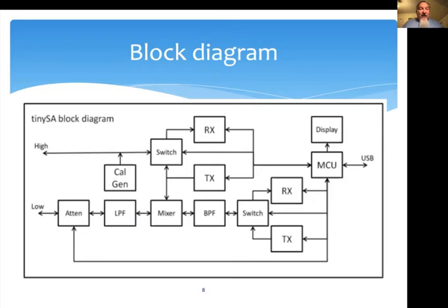So there is this attenuator as a first stage. Also, as I'll mention later on, the attenuation is quite important to condition the input signal into a range which reduces, as far as possible, the presence of artifacts and spurs. It then goes into a low pass filter according to the frequency range or the measurements that you're doing. And the purpose of the low pass filter is mainly to cut out any noise at higher frequencies that you're not interested in. So it's kind of a noise reduction thing there.